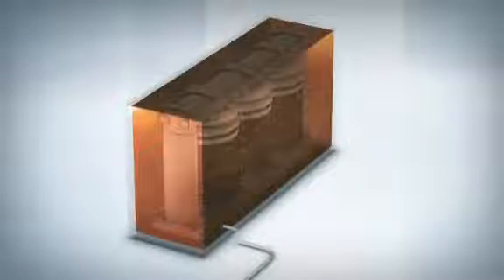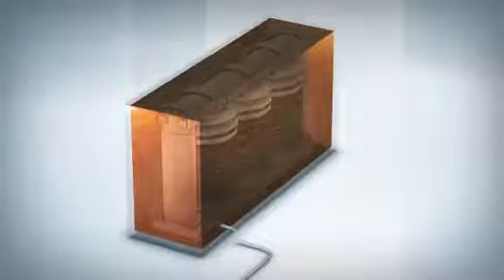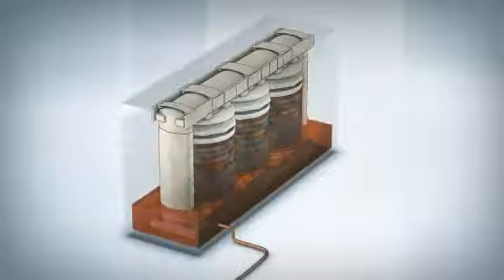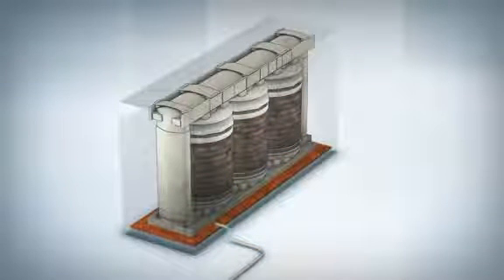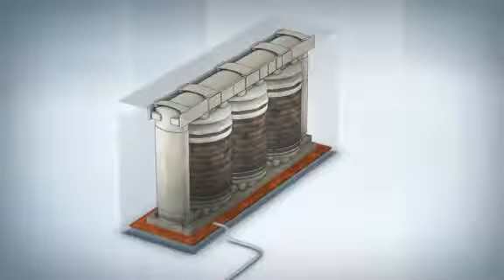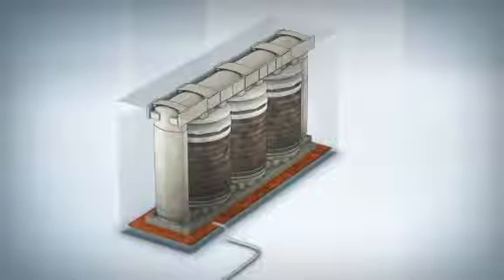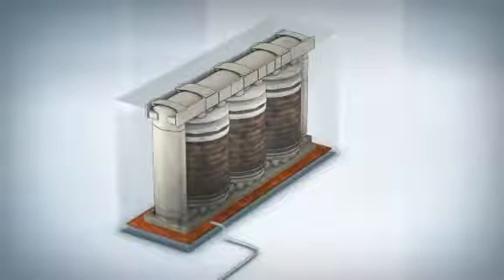There are a number of ways to prevent the oil from decaying. One can switch off the transformer and change the oil, a costly and considerably ineffective process. However, the oil can be regenerated during normal operation, a process that is far more than just environmentally friendly.